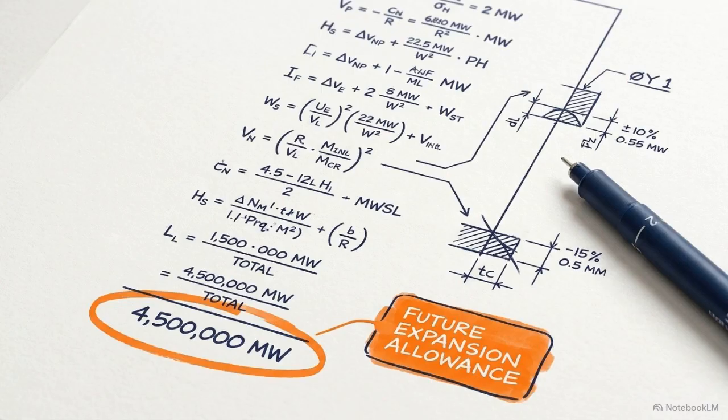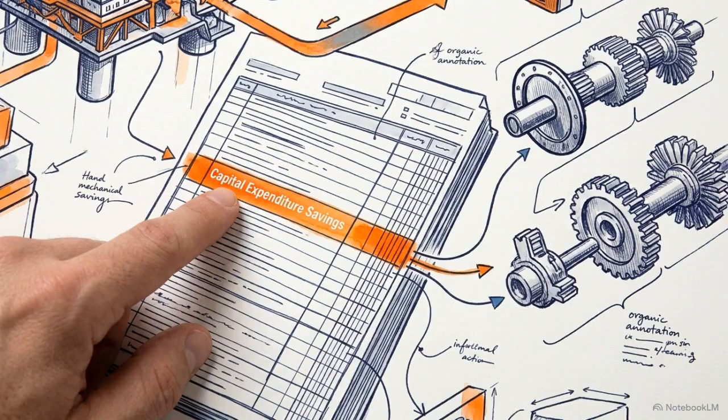board. Even with this precision, engineers typically add a 10 to 25% margin to that final TPPL figure, specifically to accommodate future plant expansion, as oil and gas reservoirs behave unexpectedly. Calculating the TPPL strips away the paranoid assumption that every motor and light will run at exactly the same time, preventing massive capital waste while maintaining strict safety margins.